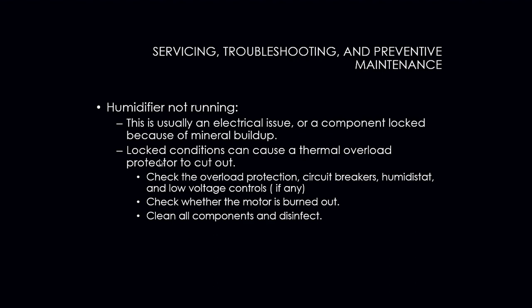It's usually going to be an electrical issue if the humidifier is not running. Okay, so we have to make sure that our components are not seized up. We have to make sure that the wires connected to it are actually connected. We need to verify that we actually have power going to our components. We also need to make sure that there is not a lot of mineral buildup inside a humidifier. A locked condition like a motor seizing, or a solenoid valve not delivering water to the humidifier itself, can all be caused by mineral deposits.